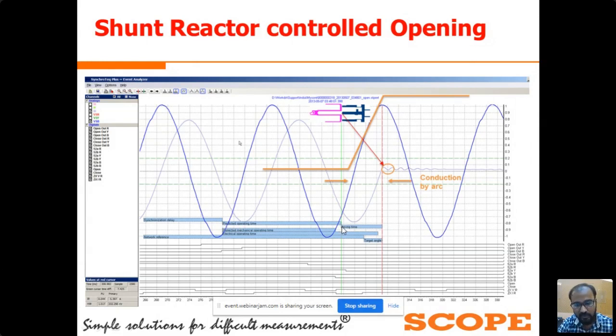After this point we can see this is an arcing zone. This is the arcing time. From this point to this point, this is the breaker opening operating time. At this moment, at my cursor position, the CB contacts are separated physically from each other. At this moment, the dielectric strength between the CB contacts is less than the system voltage. So due to that, the current continuously flows through the system.